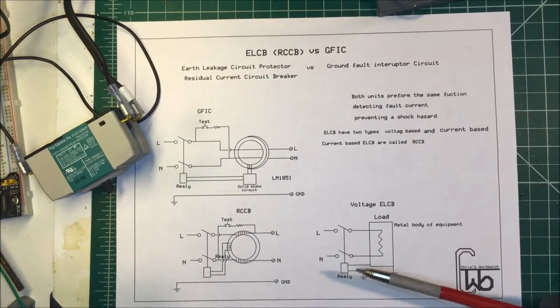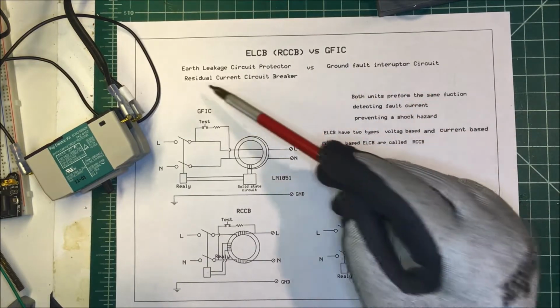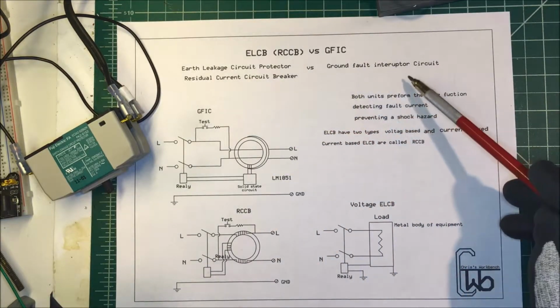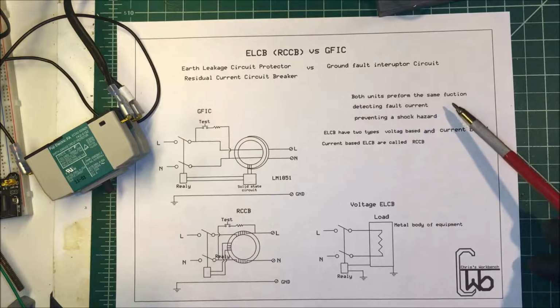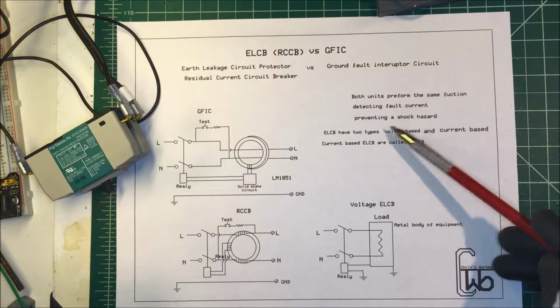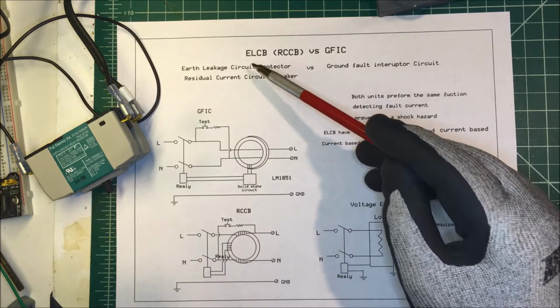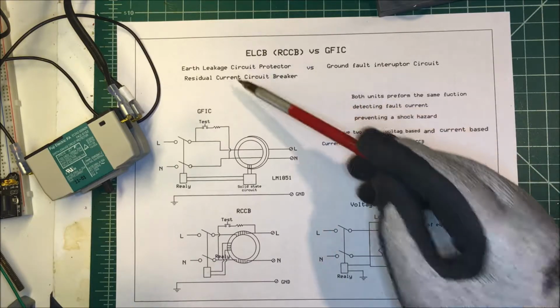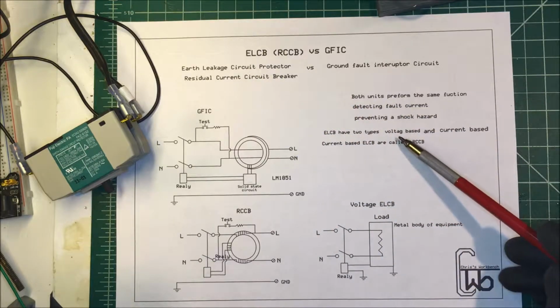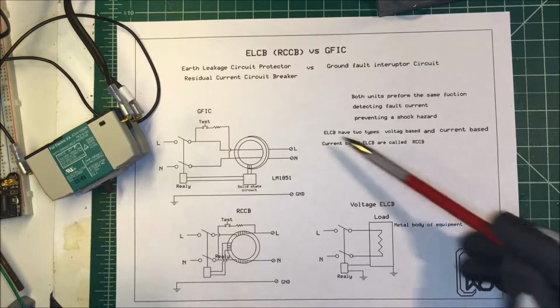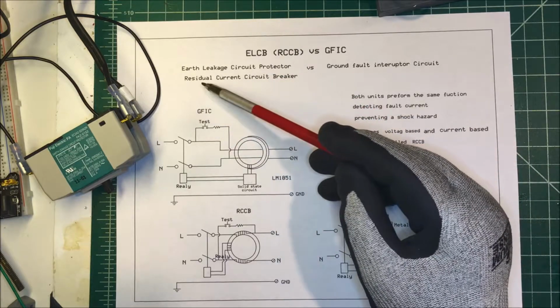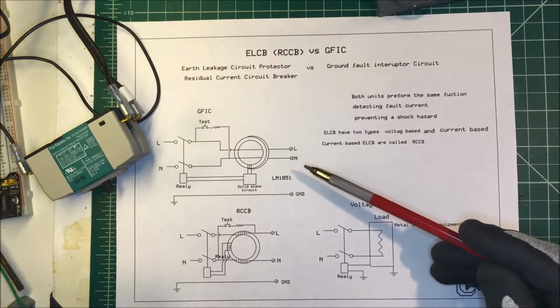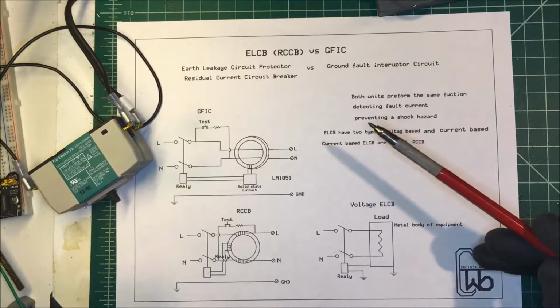Let's talk about an ELCB and a GFIC, an earth leakage circuit protector and a ground fault interrupter circuit. Now they both perform the same function, detecting fault currents and preventing a shock hazard. We'll take a look at the ELCB. Now they come in two different varieties. One is based on voltage and the other one on current. The current ones are residual current circuit breakers. That's what this actually is here.